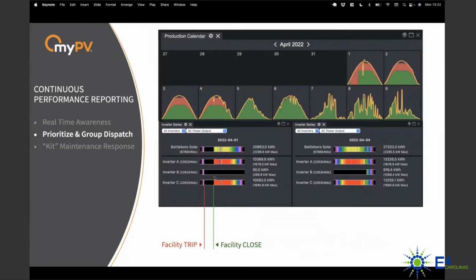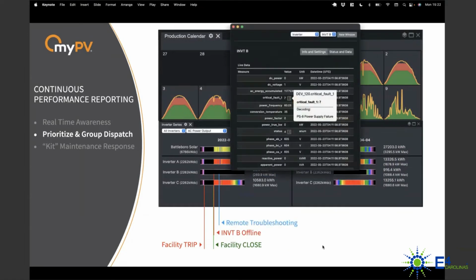But when we closed that recloser, inverter B did not come back, and it stopped generating. So again, using some tools here, we were able to take a look at what happened with that inverter. It was throwing a critical fault.